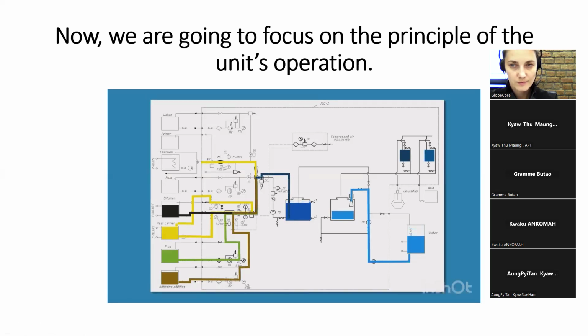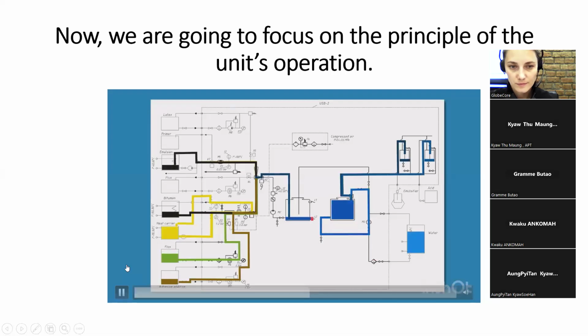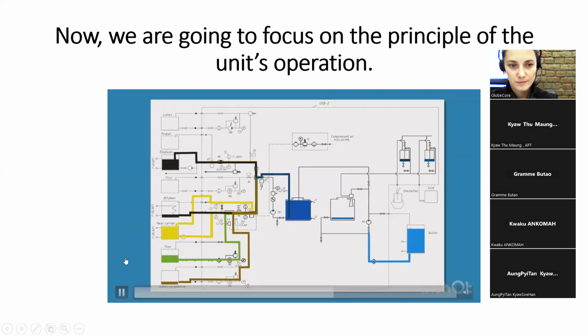There are top and bottom level sensors in the first tank to monitor the water phase level. When the liquid level drops below the bottom level sensor, an audible alarm goes off. The operator is warned of the need to switch the valves to pumping the water phase into the consumption tank. If the liquid level has not resumed the sensor level after a preset time interval, the unit will automatically shut down to prevent alarm conditions.